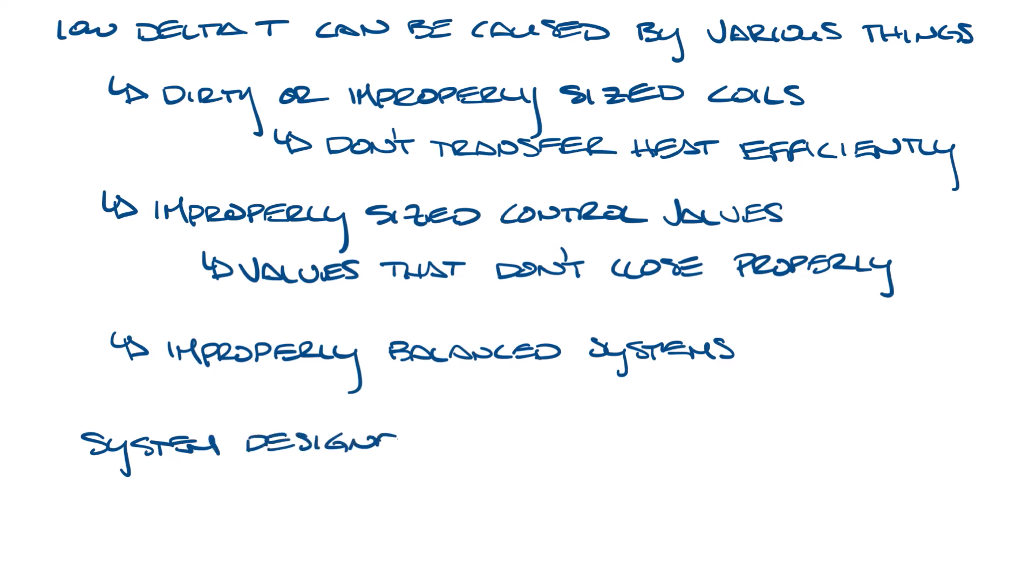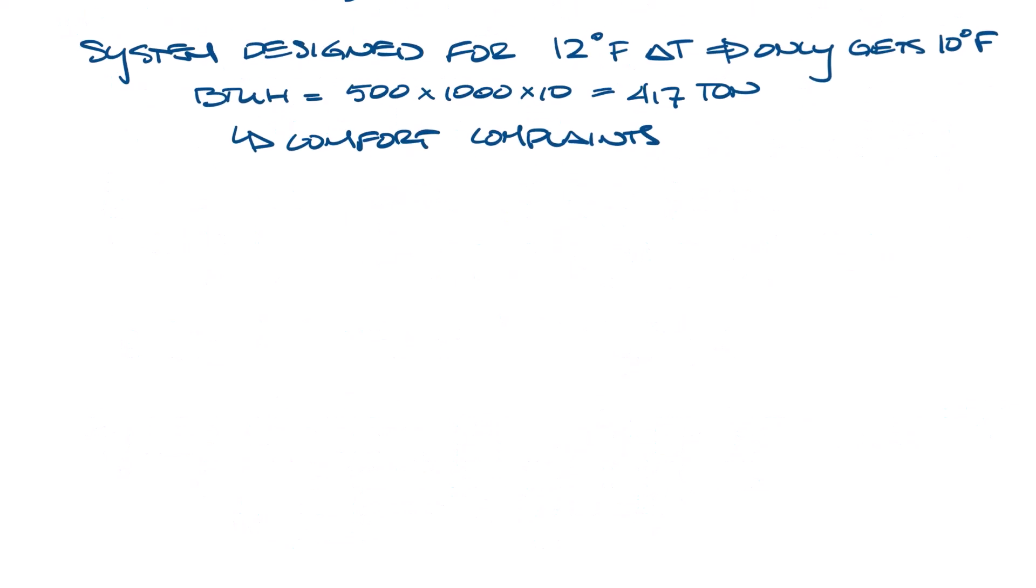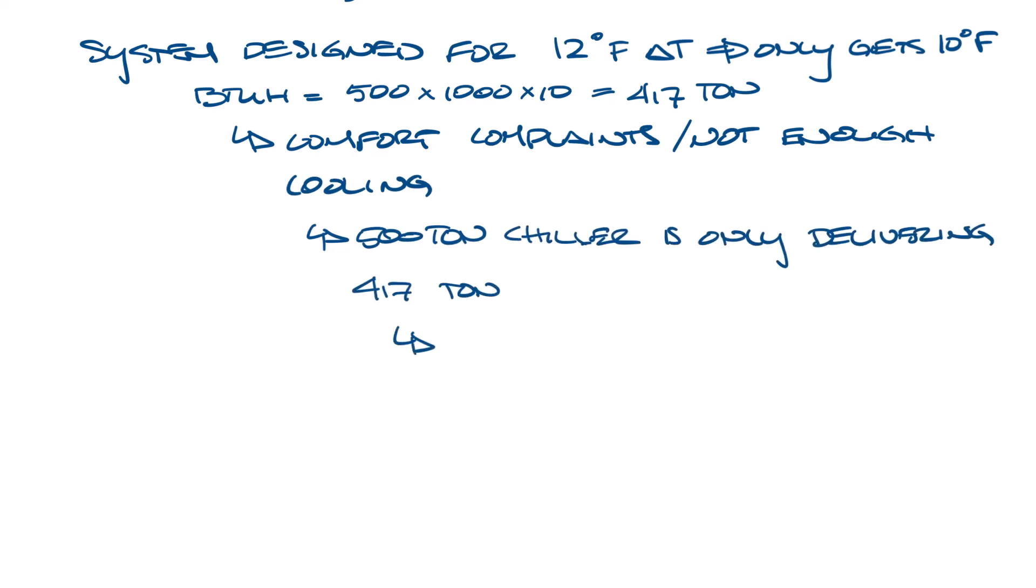In my example, I made the math easy, but if the system was designed for 12 degree delta T, and let's say it's only getting 10 degree delta T due to oversized coils, then if we do the BTU math here, we get 500 times 1,000 times 10, and that gives us 417 tons. In this situation, you might get comfort complaints about not having enough cooling in the space, because your 500 ton chiller is only delivering 417 tons of cooling. And this might result in someone increasing the pump speed, or even another chiller being cycled on to meet the load. And both of these would be a waste of energy.